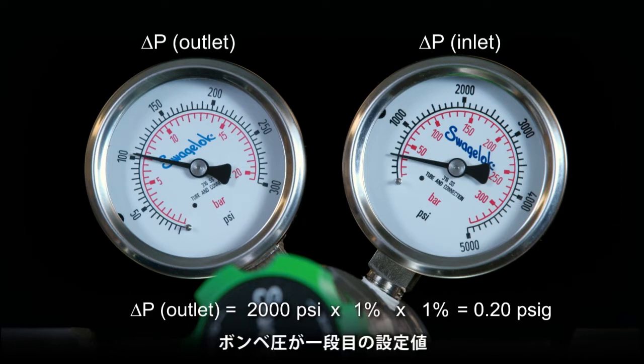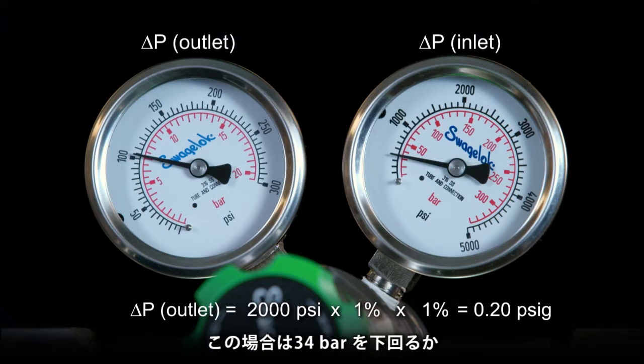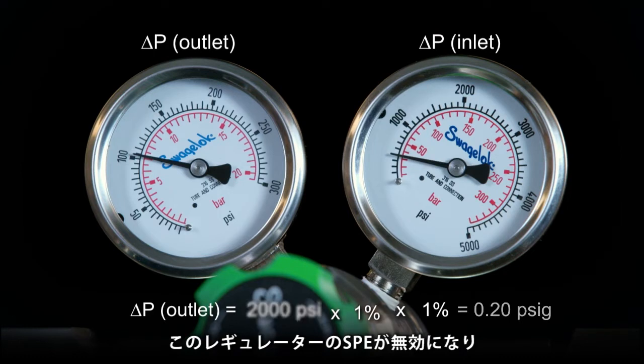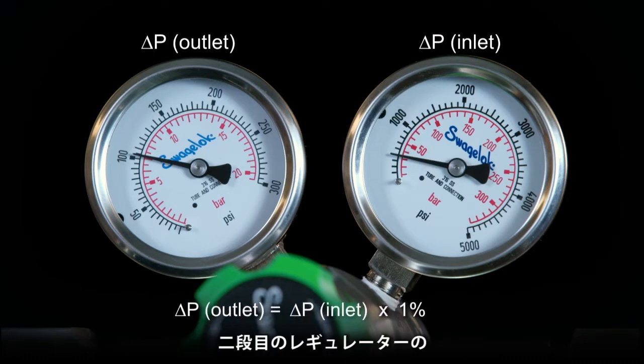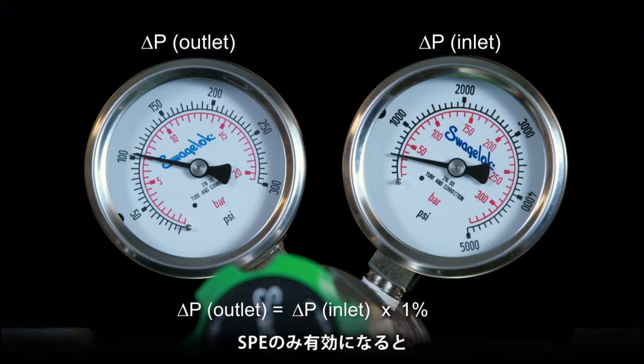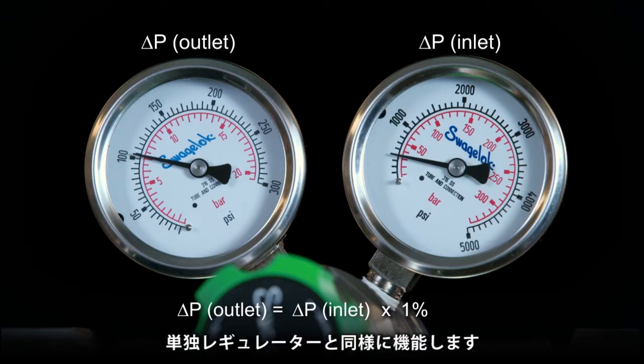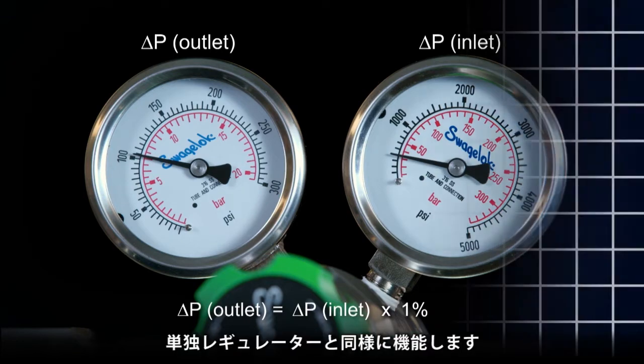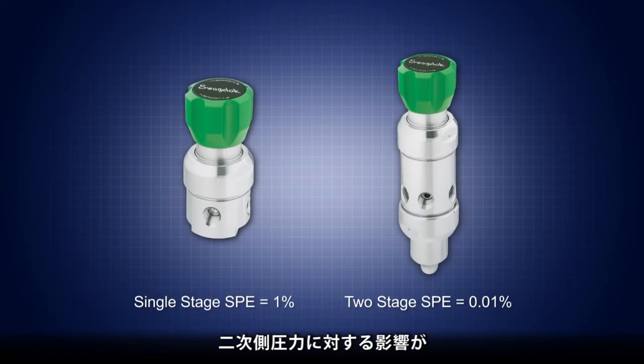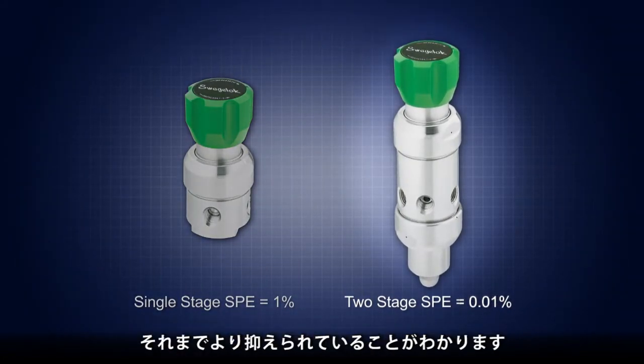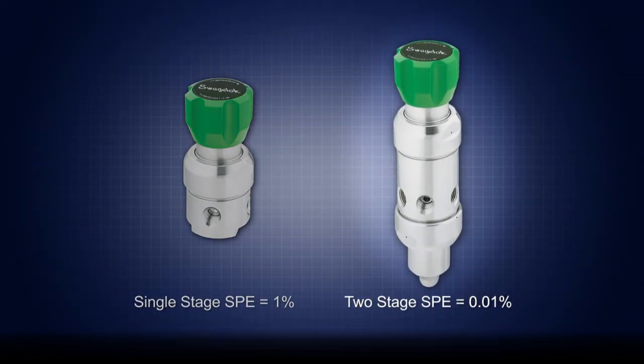Once the cylinder pressure drops below the first stage setting, in this case 34 bar or 500 psig, the SPE of this regulator is no longer applicable and only the SPE of the second stage regulator is taken into account. Then the assembly will behave like a single-stage regulator. Notice how the effect on the outlet pressure is lessened from the previous regulator arrangements.